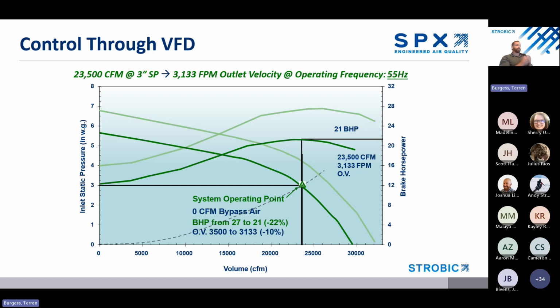So when we go to control through VFD, control through fan modulation, right? The Strobic Safe Controller is designed to prioritize safety first and foremost as a life-critical device, but it also has the logic to consider efficiency in your lab exhaust system. So traditionally, like I was saying, with fans running at fixed speeds and relying heavily on bypass air, that meant a lot of wasted energy. With the Safe Controller, the system constantly monitors real-time conditions like building pressure, outlet velocity, and other inputs, and it makes precise adjustments to fan speed safely and dynamically using the drives and modulation of the damper. It's all against the proprietary sequence of the Safe Controller.